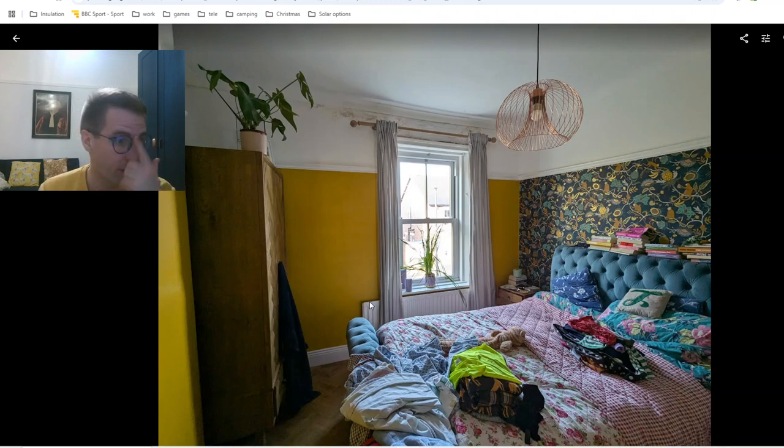This is a single panel radiator. We've now got double glazed sash windows, which wouldn't have been new; it would have been single pane wood, and so it retains a lot more heat. So we could have a radiator that's a little bit wider, but it's a K3, and that would hang off the solid walls absolutely fine. It wouldn't be a problem for the floor.